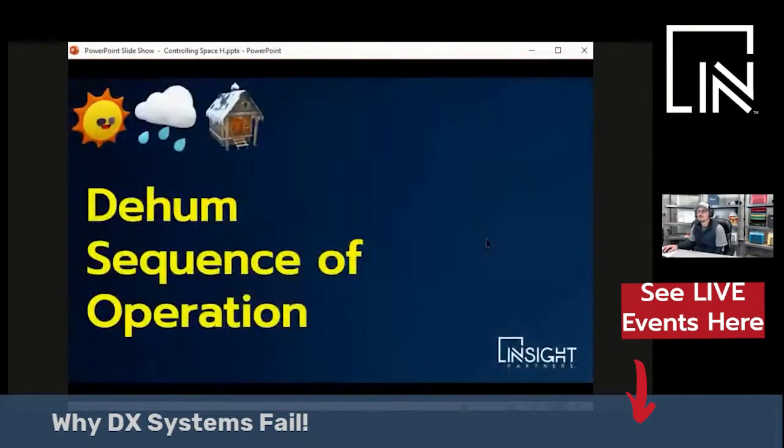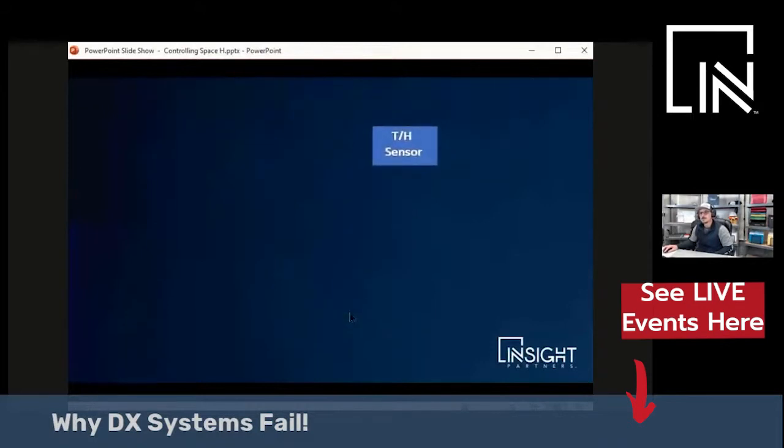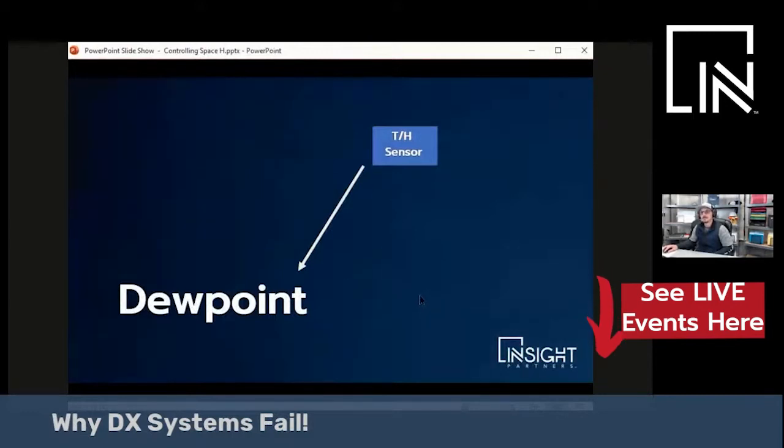Normal systems aren't designed to do that. So let's look at the dehumidification sequence of operation when you have a true unit that's designed to control temperature and humidity over all load conditions. I've added another component to this system we looked at earlier, which is called a reheat coil. We're also going to add, instead of a temperature sensor or a thermostat in the space, we're going to do a temperature and humidity sensor combo. So what that allows us to do is measure the actual dew point in the space. Dew point is a very good indicator of the actual amount of moisture in the space, much better than relative humidity.